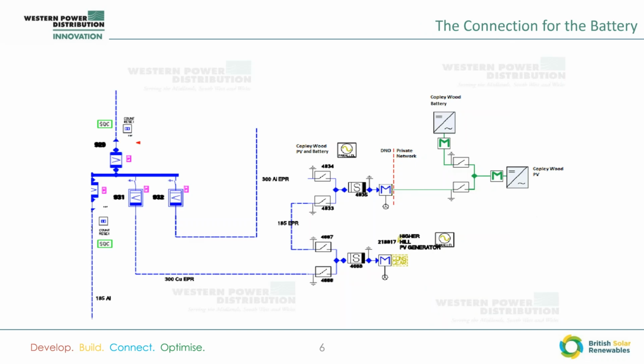This shows the single line diagram to demonstrate how the battery is connected to the network. So you've got the bus bar of Millfield primary substation on the left there, and then the blue 11 kV feeder running to Higher Hill PV generator. And then the Copley Wood PV farm was connected into the spare ring main on the DNO side. And then on the private network side, the Copley Wood battery was connected behind the meter on a spare ring main unit there. And then both of them had power quality meters installed so that they could be metered separately.